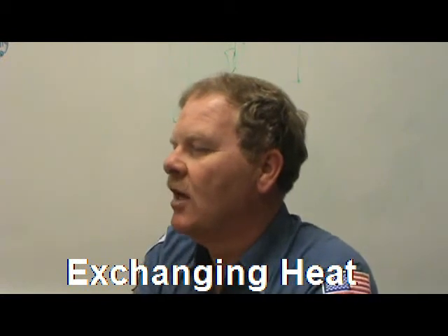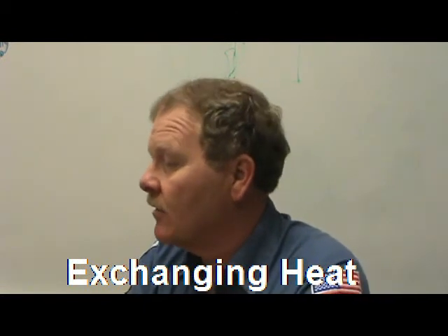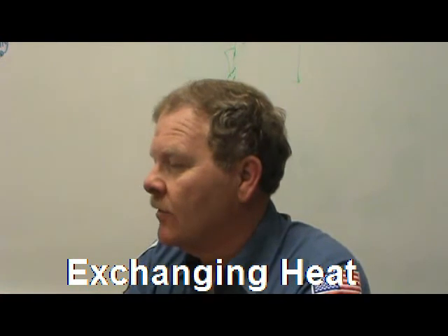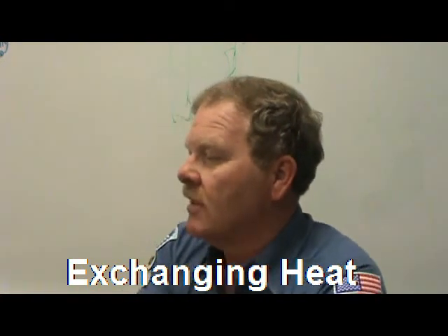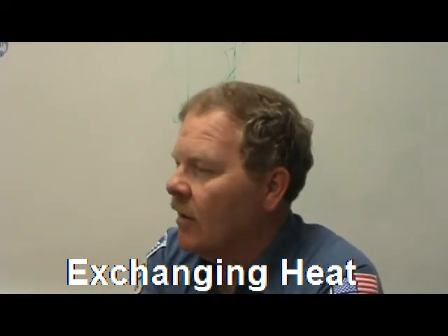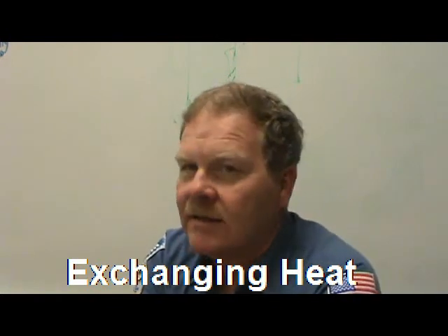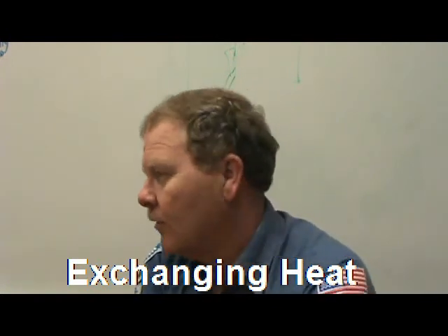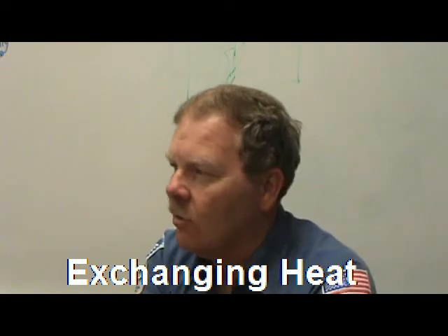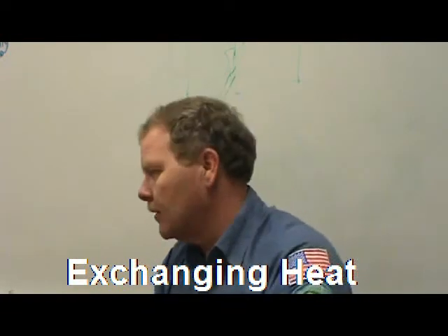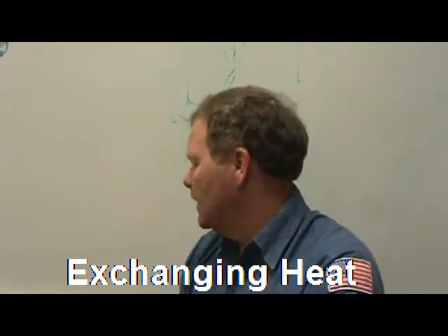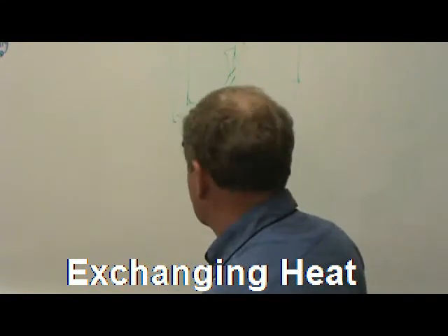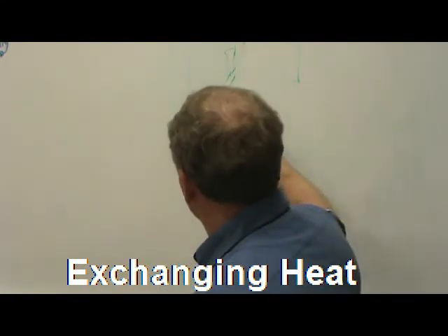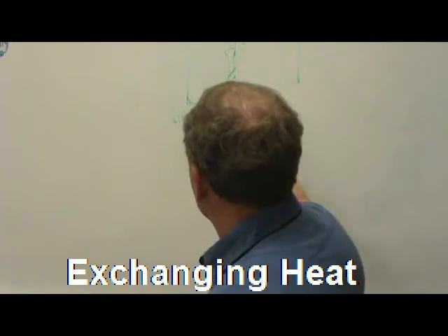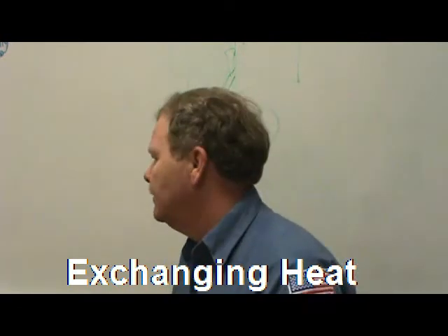Okay, some use a belt drive along with an electric motor. Non-conductive refrigeration oil must be used with AC compressors utilizing an electric drive motor. You know what that oil is, that non-conductive refrigerant oil? They don't want the refrigerant oil eating the insulation off the wires inside the compressor, because it's going to be in there with them. So you have to use an oil, last I heard, was ND11.